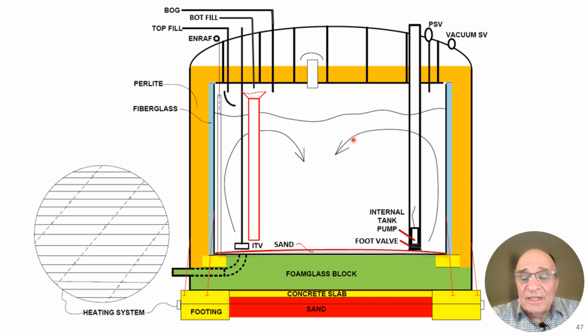And this continuous circulation means that the temperature here is approximately the same as the temperature here. So this is saturated LNG, and this is subcooled LNG. And you need subcooled LNG to feed your pumps. And there's two methods of feeding pumps. You can have an external pump, which is here, and which would require a bottom penetration to your tank. So this would be feeding external pumps. They're external to the tank. And you have a bottom penetration.